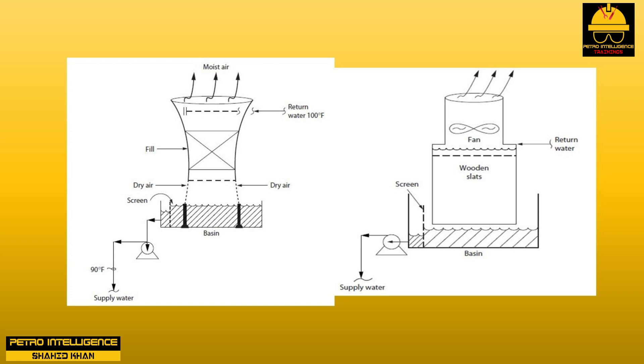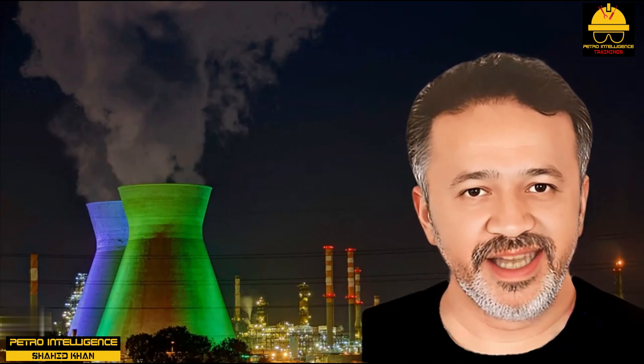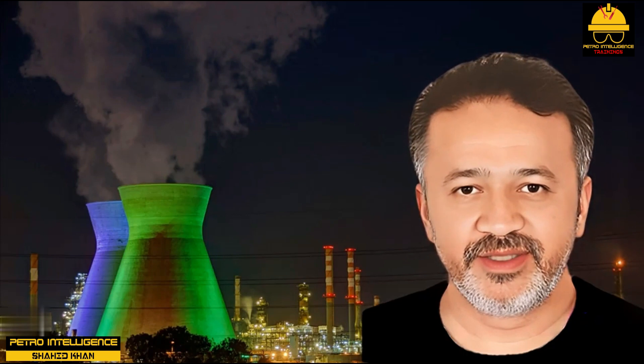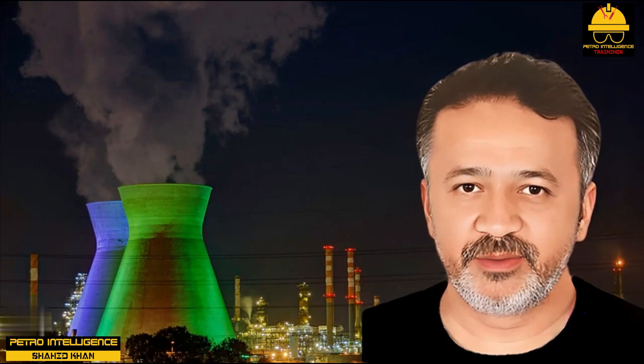A few tenths of an inch of water draft may be developed in natural draft towers. The much smaller induced draft cooling towers used in process plants generate air flow using large induced draft fans. Regardless of the type of cooling tower, the same criterion is used to gauge performance: the approach of the cooled water temperature compared to the air wet bulb temperature.